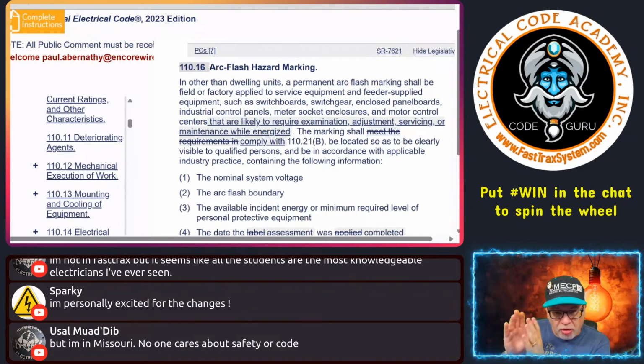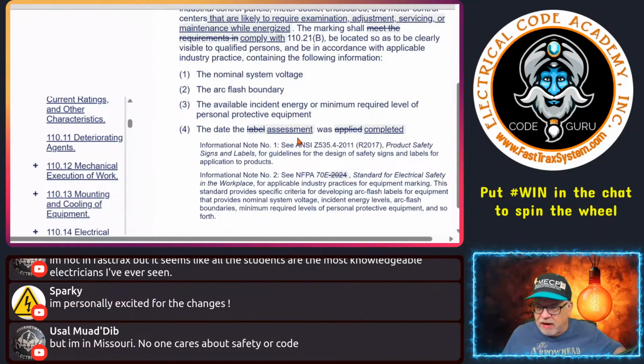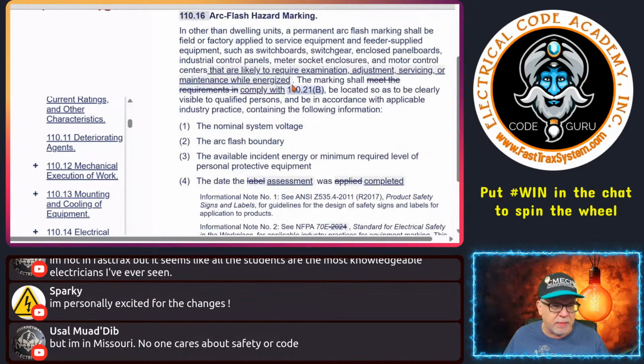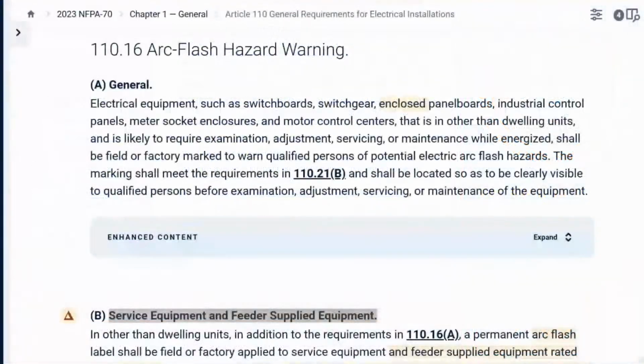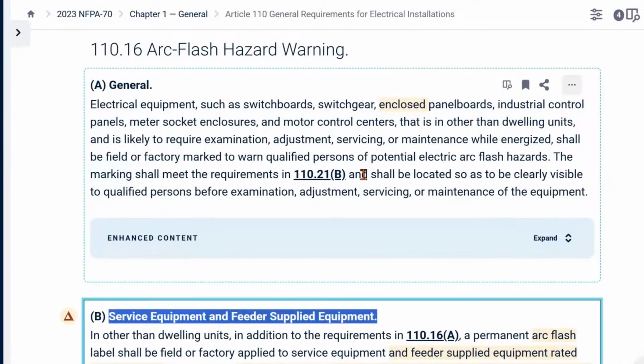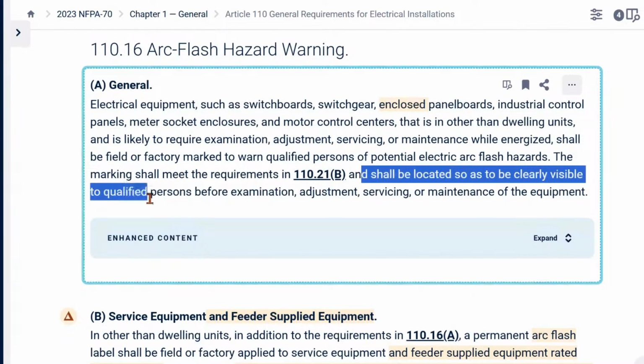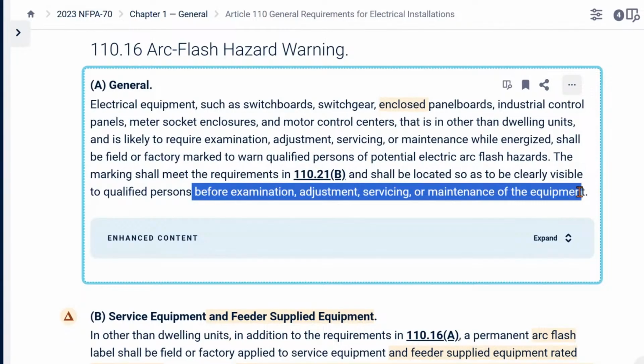I think personally, all those items you see there probably do meet the list of where that type of adjustment, servicing, or maintenance could occur while potentially energized. Now, the big change here: the language was still there, just moved around. If you look back at the 2023 version, it's right here: clearly visible to qualified persons for examination, adjustment, servicing, maintenance of the equipment. So it's not new, it just got moved out of an A and into the general statement of 110.16.